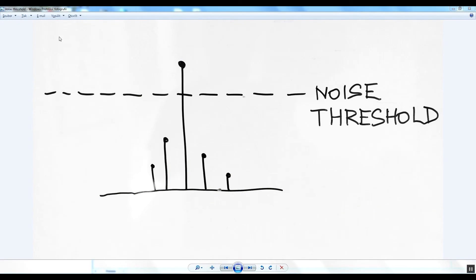Maybe I should explain in more detail how a peak is found. The peak is 5 spectrum lines where the highest one is in the middle and the sideband lines decrease. We also define a noise threshold. The peak exists only when it is higher than this threshold value. Usually this limit is equal to 1% of the total RMS of the spectrum.